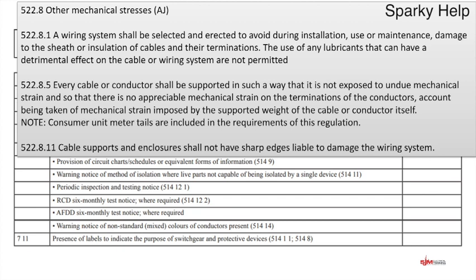So basically, a terminal must not hold a cable in place, which for years effectively that's what we've been doing. Consumer units, it's the terminals that hold the cable there, and we've all been guilty, and there's many of them. The photos I just showed you, terminations holding them. The regulations haven't changed in that sense. What they've just added is that note there that said that tails must be clipped.